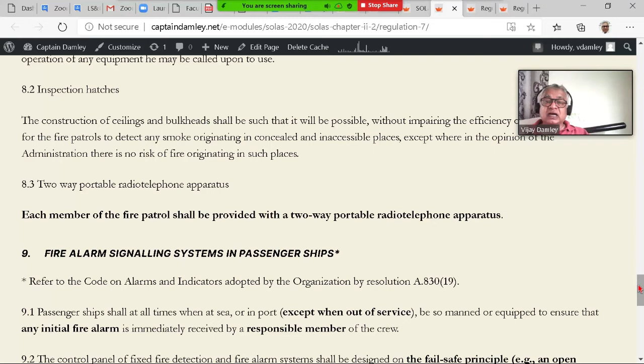This fire alarm signaling system on passenger ships is something you must understand. When anything initiates fire alarm, it is received in the control station by a responsible member. What he does is, he will generally initiate alarm to some crew member, not give the alarm straight away, because you do get a lot of false alarms. So the idea is, in case there is a false alarm, you don't want to activate full firefighting, because passengers can get totally confused and panicky. So on passenger ships, you have a system which delays the fire alarms.